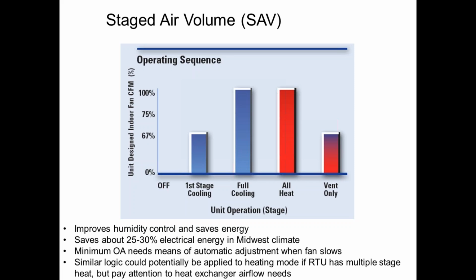Some folks ask why we don't do multiple stages on the heat. There are numerous reasons for that, but the main reason is the Economizer controller has to have the ability to have dual minimum airflow set points. Because if I slow your fan down and I don't change your Economizer minimum position, you're going to get less code required ventilation air. So I have to have an Economizer controller that can intercept these signals from the thermostat and be smart enough to say, oh, you want one stage or two stages of cooling? Oh, I go to a different minimum position for those two scenarios. And right now, the only Economizer controllers like that do 2 minimums at most. No one does a 3 minimum scenario yet for Economizer control.